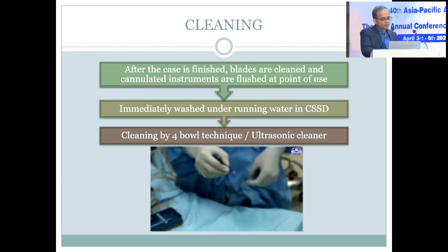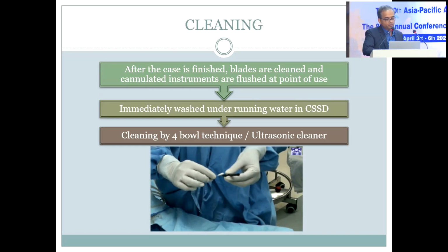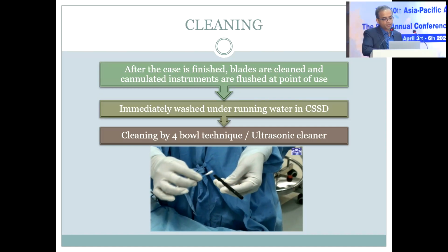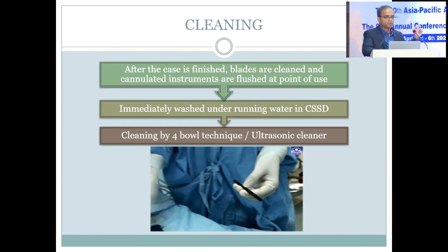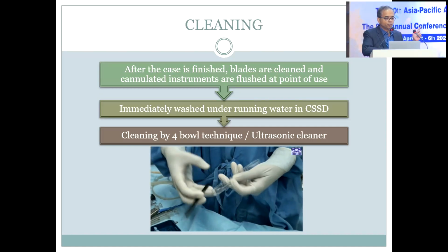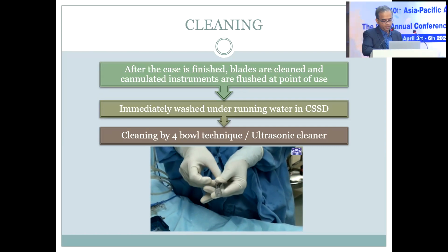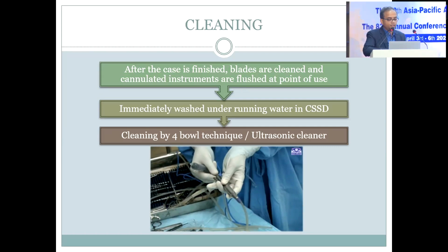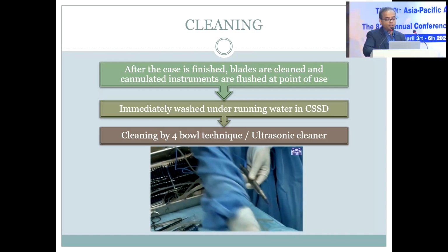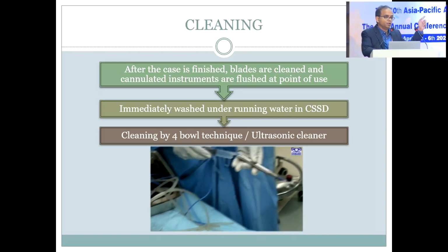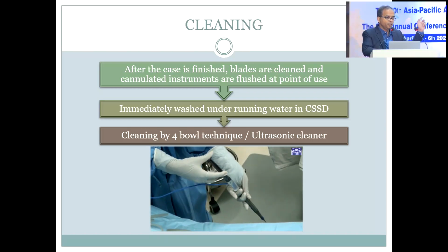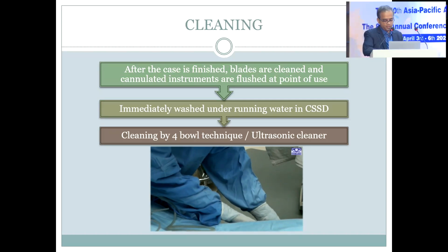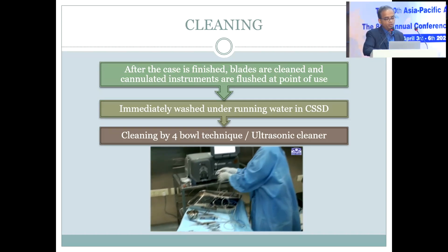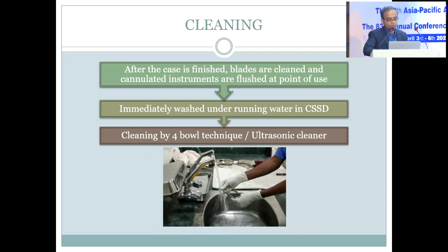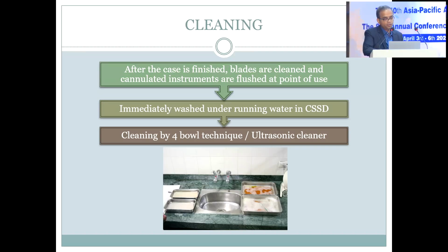So this is how the instruments are being cleaned. The blades are cleaned, and cannulated instruments should be flushed. For example, your phaco probes should be flushed immediately. And these instruments are then washed under running water. So they are taken out from the waste corridor, and they are then cleaned in the CSSD. And later on, the cleaning by 4-bowl technique or ultrasonic cleaner. So this is the cleaning that is being done in CSSD, followed by the 4-bowl technique.